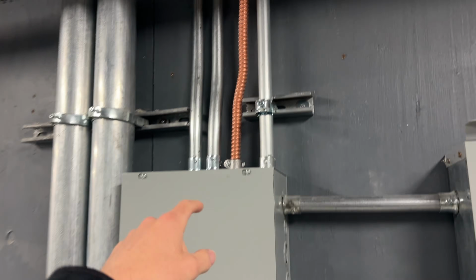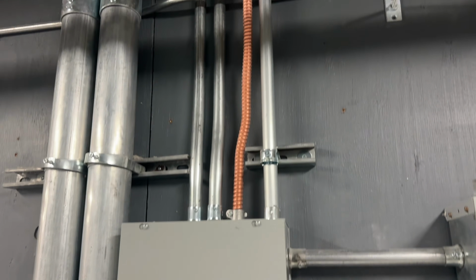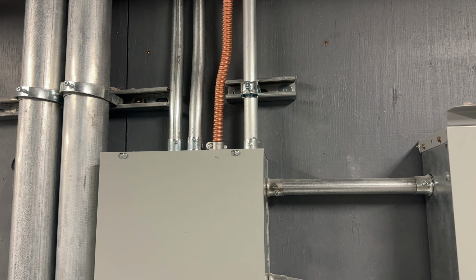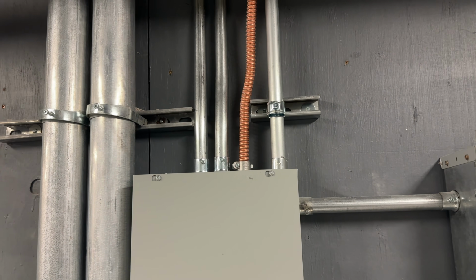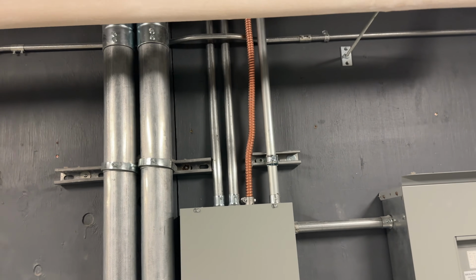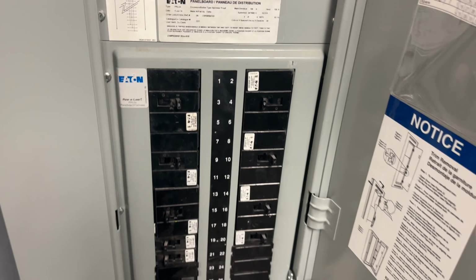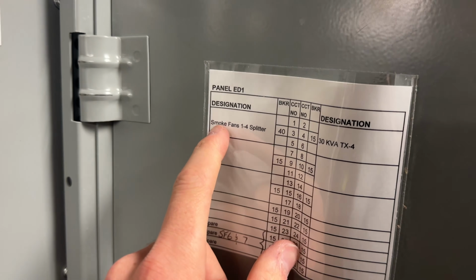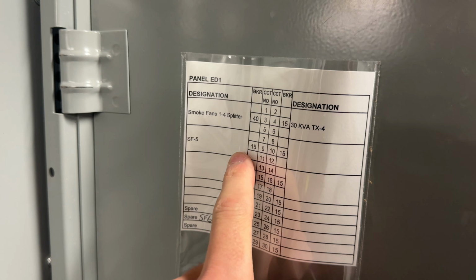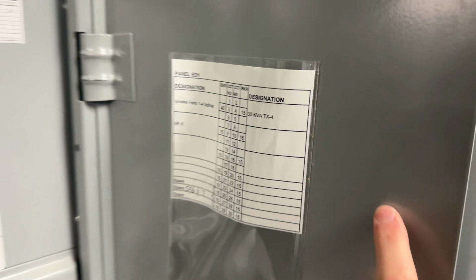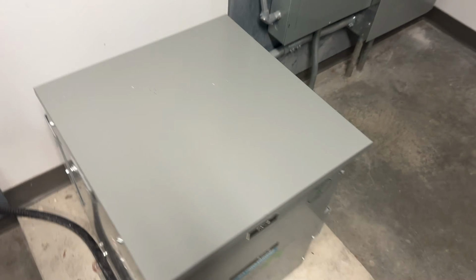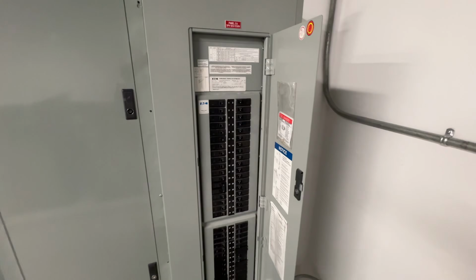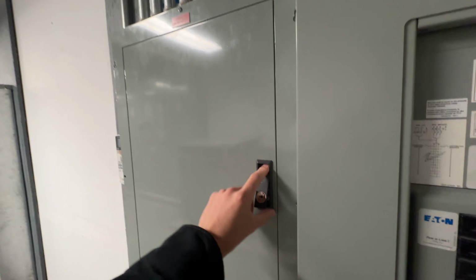You can also see that mineral insulated cable. That is doing one of the supply fans. It needs to be that to withstand fire, as it's going through multiple fire zones and it needs to have survivability for a long time. You can see this panel here is doing some of our smoke fans and our 30 kVA transformer, which then comes out of this transformer, does this 120/208 panel. This does a lot of our lighting, and that goes into this lighting control panel.